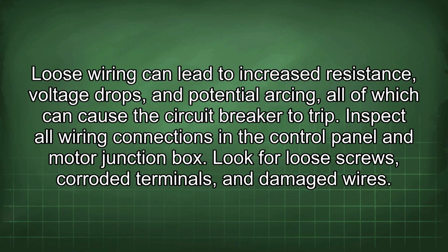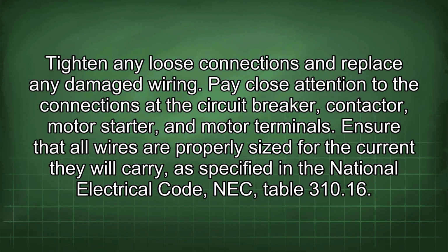Loose wiring can lead to increased resistance, voltage drops, and potential arcing, all of which can cause the circuit breaker to trip. Inspect all wiring connections in the control panel and motor junction box. Look for loose screws, corroded terminals, and damaged wires. Tighten any loose connections and replace any damaged wiring. Pay close attention to the connections at the circuit breaker, contactor, motor starter, and motor terminals.